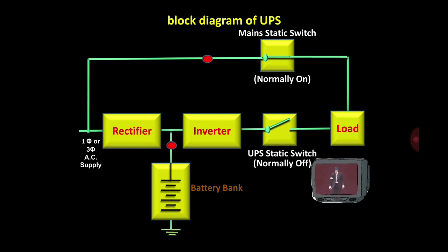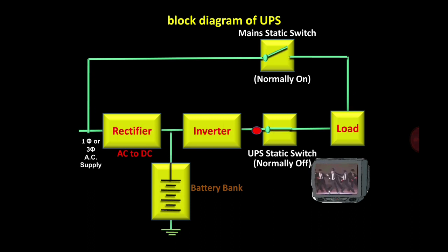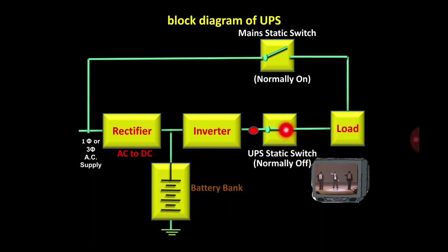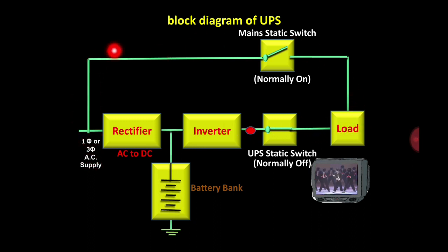Now, if for any reason the main supply is not available, the main static switch gets open and the UPS static switch gets closed. The moment the main supply is not available, the UPS static switch closes and the main static switch opens. The load is still receiving supply — now through the inverter. The battery provides DC, and the inverter converts that DC into AC, so the load gets continuous supply even when the main supply is not available.